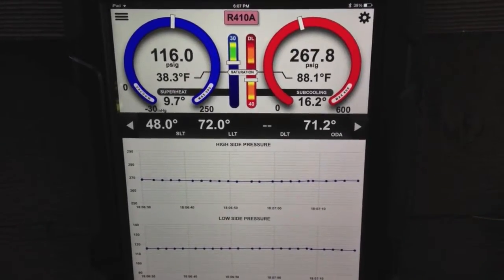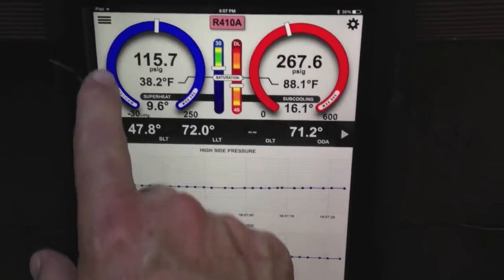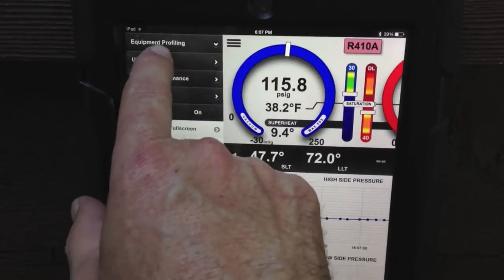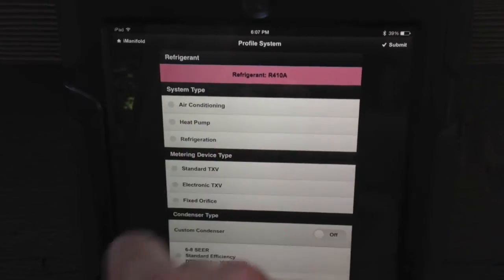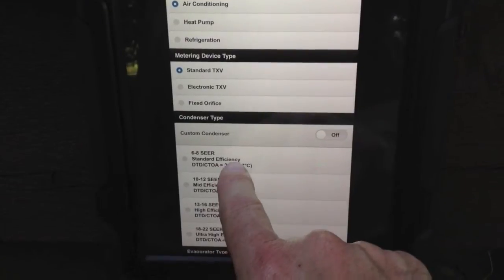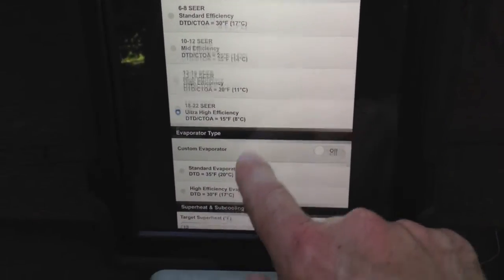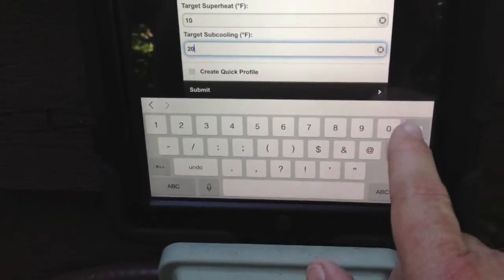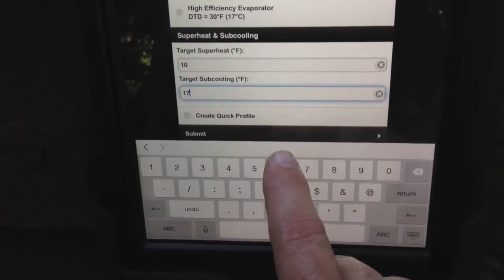Now that the system's settled out, I'm going to show you how we profile the system. I'll hit profile, swipe it over, equipment profiling, profile a new system. We're going to set this up as air conditioning, standard TXV, ultra high efficiency, standard evaporator. Our target subcooling is 17 and we'll leave our current one at 10. Hit submit.